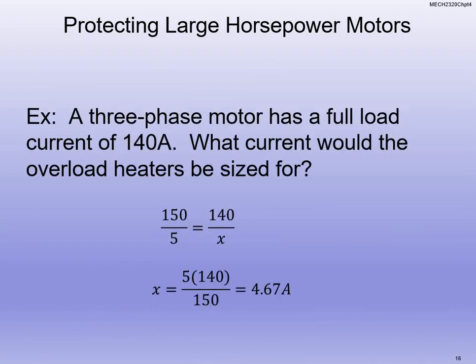So, a small calculation here. Let's say we have a three-phase motor that has a full load current of 140 amps. What current would the overload heaters be sized for? We take that 150:5 ratio for the transformer, and we set that equal to 140 over X. Solving for X, we end up with 4.67 amps. So that's what the overload heaters have to be sized for. They have to be able to handle at least 4.67 amps. Normally you might size those up a little bit.